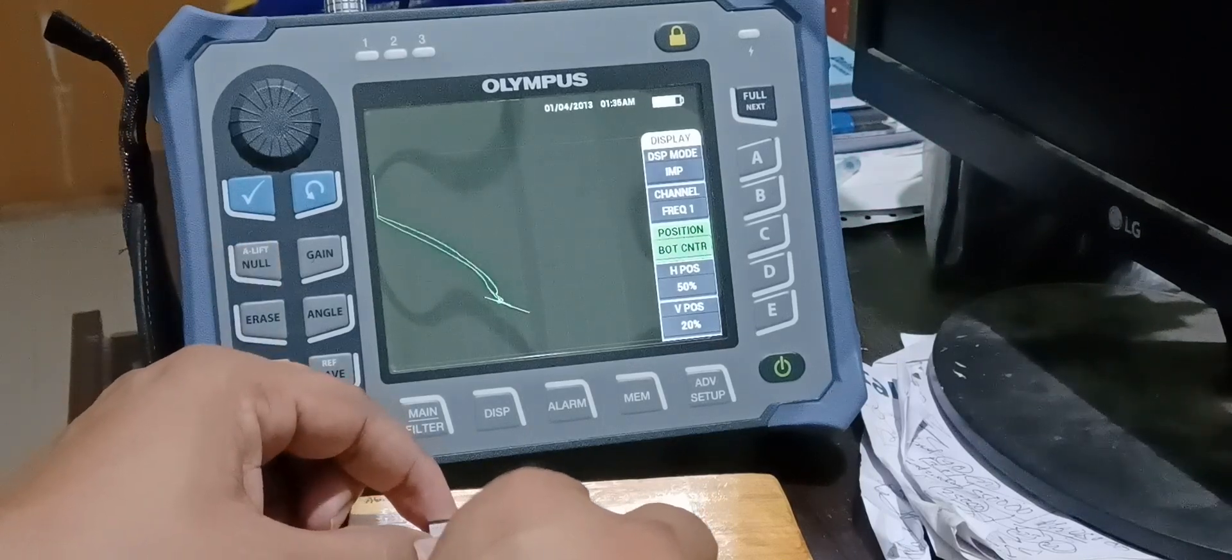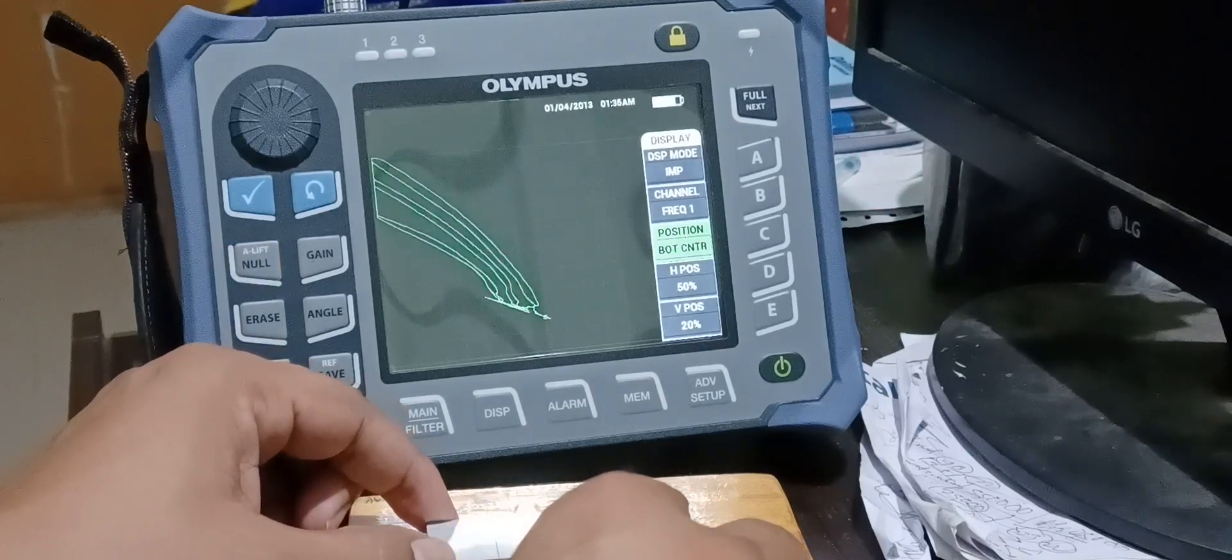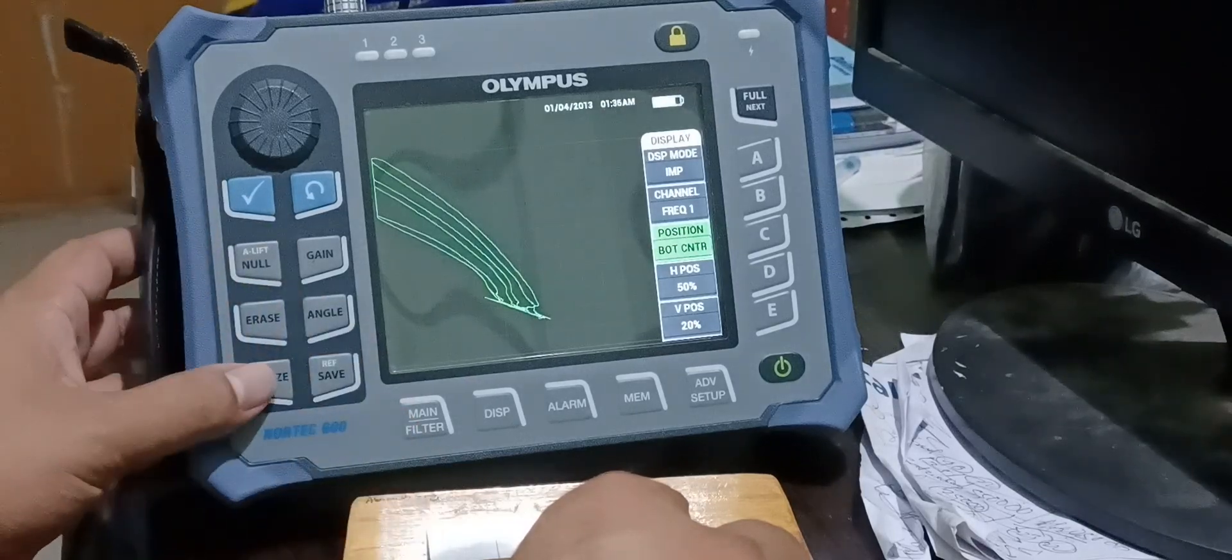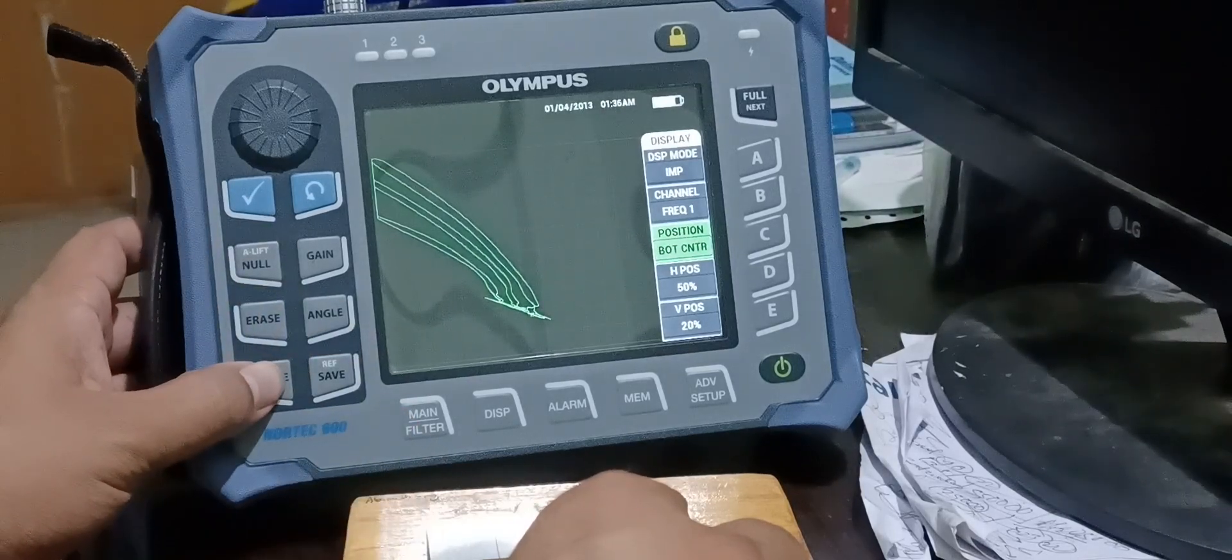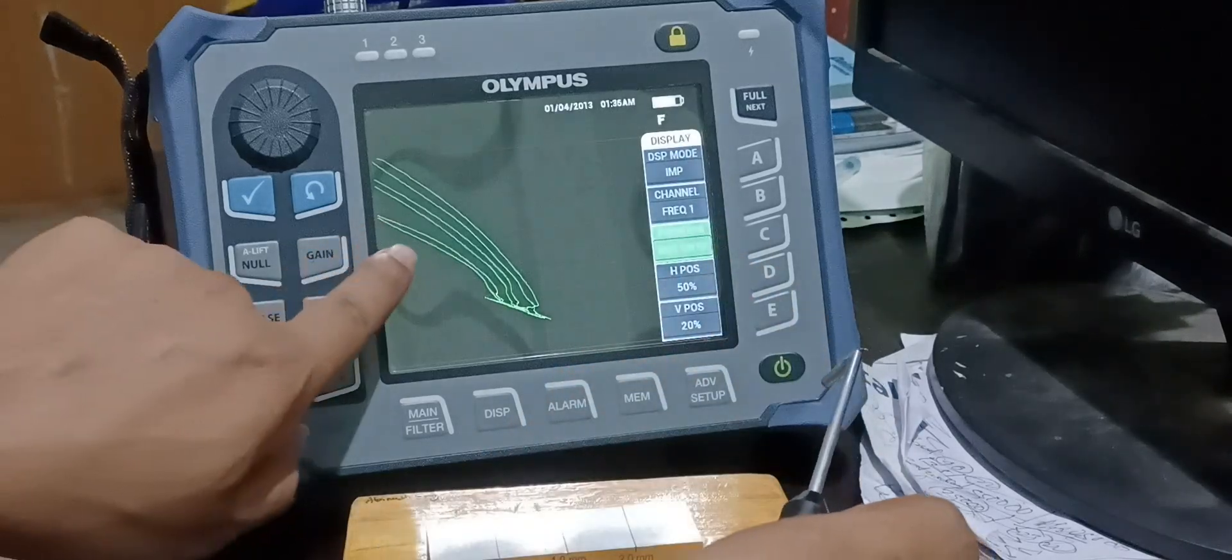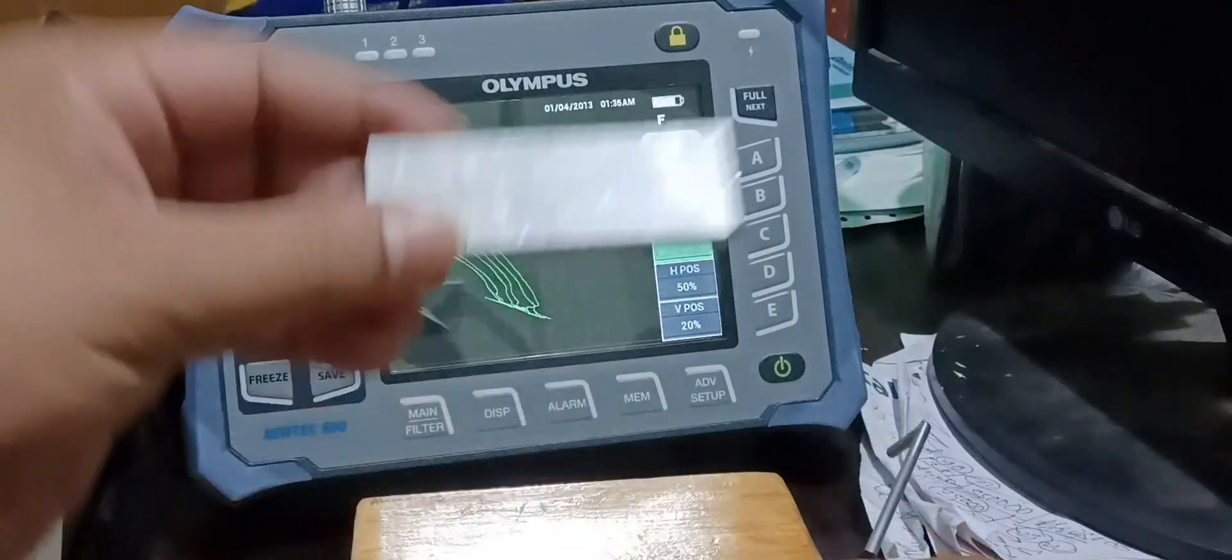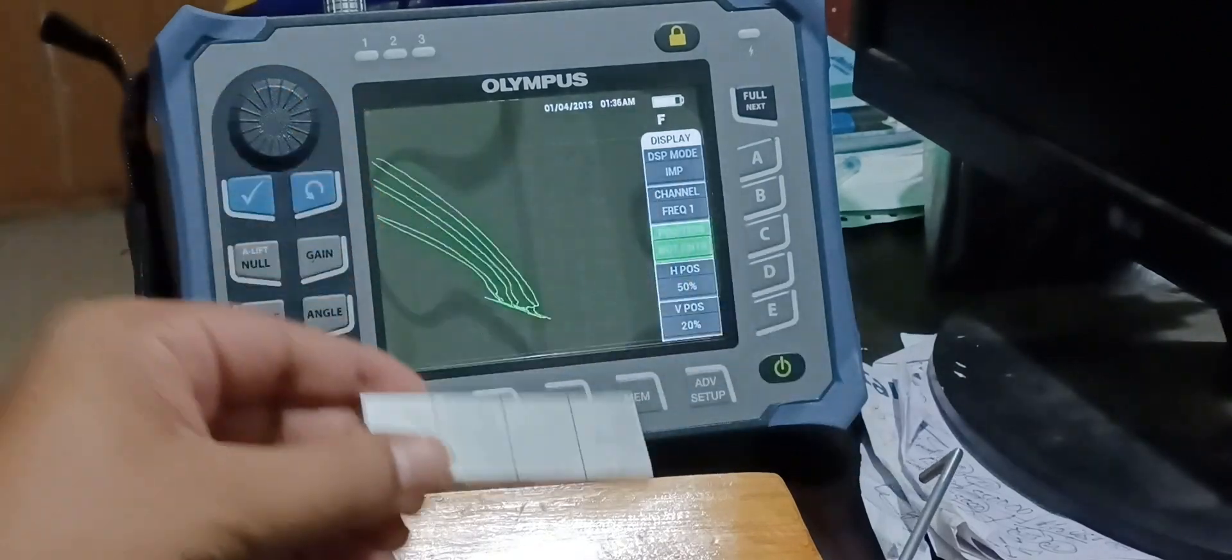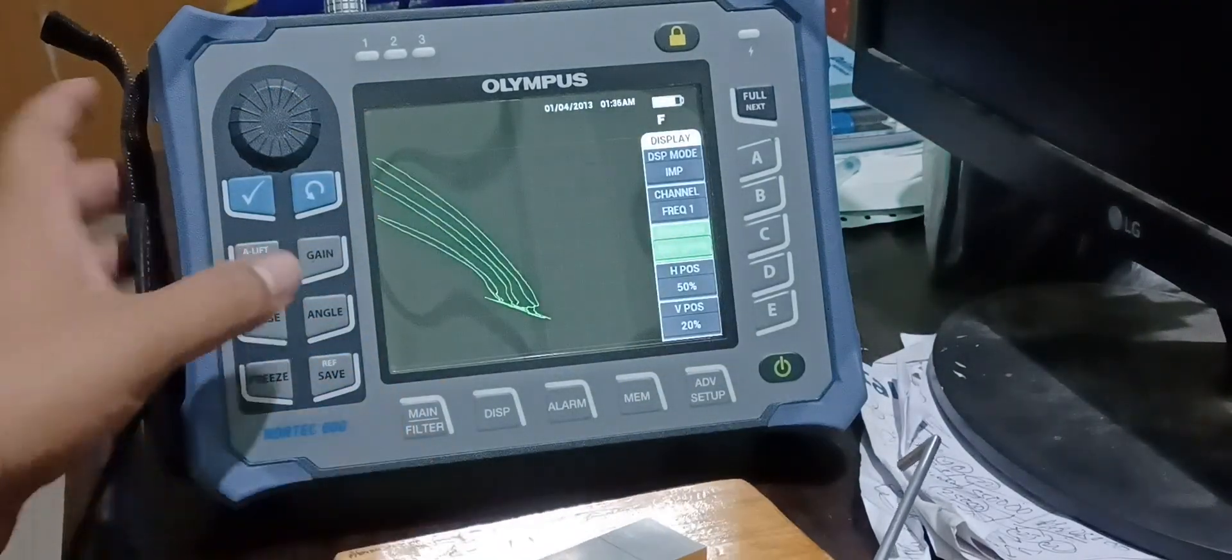My first crack, second crack and third crack. You can see, I will freeze this signal. So, these are my three crack signals coming from this surface notch standard.